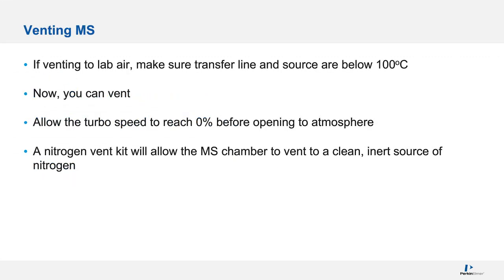When venting the mass spec, we want to make sure our transfer line and our source are below 100 degrees. If you vent to UHP nitrogen, you don't have to do that, so that saves you time. You could vent hot because you're not venting to oxygen, you're venting to UHP nitrogen. I always allow my turbo to reach 0 before I open up the system to atmosphere. Okay, let me move on.